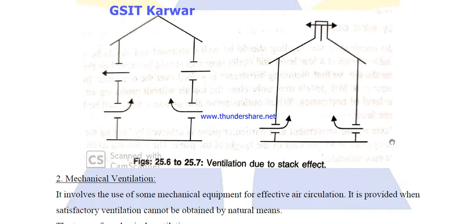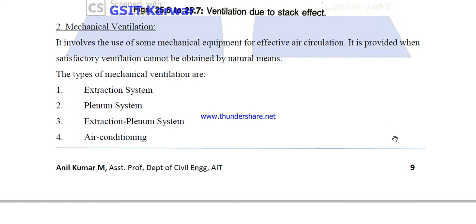Next is mechanical ventilation. It involves the use of some mechanical equipment for effective air circulation. It is provided when satisfactory ventilation cannot be obtained by natural means. The types of mechanical ventilation are extraction system, plenum system, extraction plenum system, and air conditioning. What does extraction system mean? This system is based on the creation of vacuum in the room by exhausting the spoiled inside air by means of propeller type fans, exhaust fans. This system is more useful in removing smoke, dust, odor, etc. from kitchens, bathrooms, industrial plants, etc. Exhaust fan.